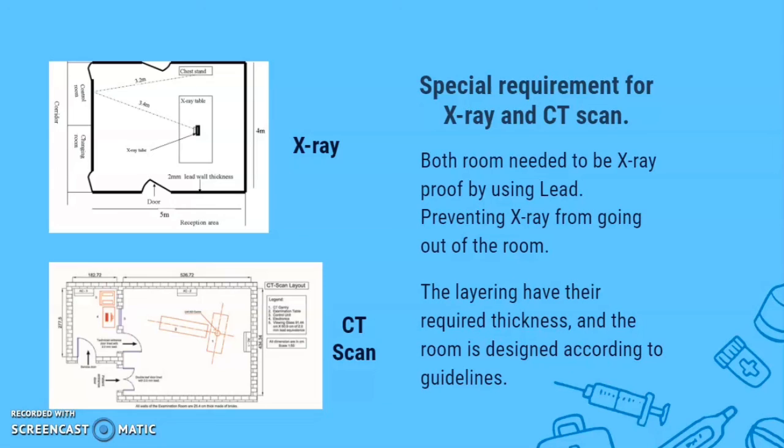This is covered under the radiation committee. This is overseen by the radiation committee of Malaysia. For the purpose of protection from the surroundings, especially protection for practitioners that will always be there most of the time. By using a suitable thickness of lead, all parts of the room, including the wall, floor, and ceiling, are covered using suitable material in order to prevent the leakage of the X-ray radiation.